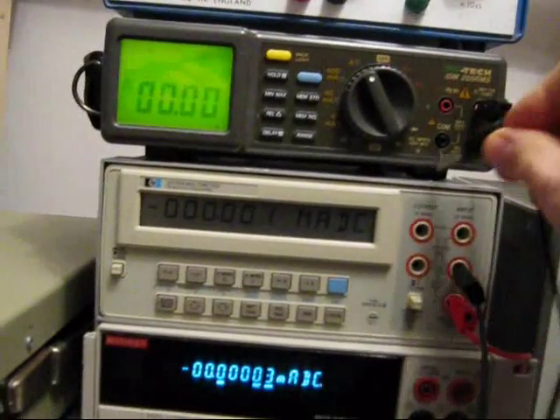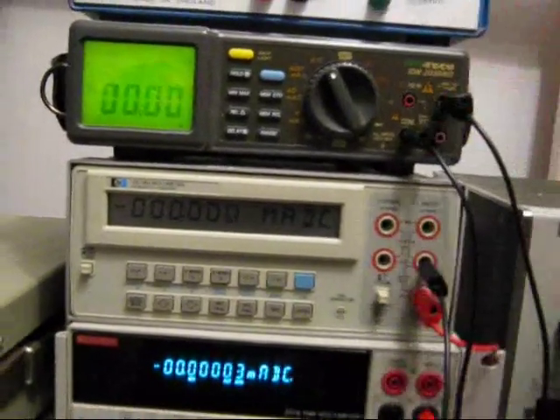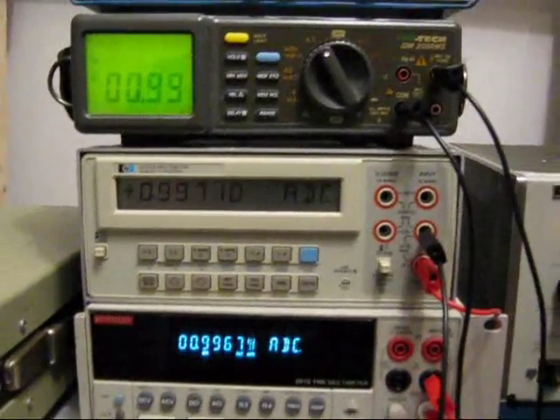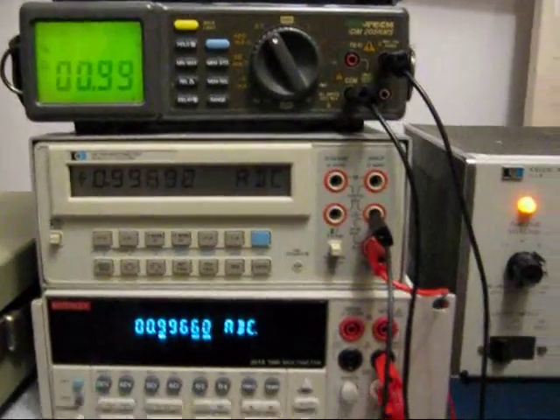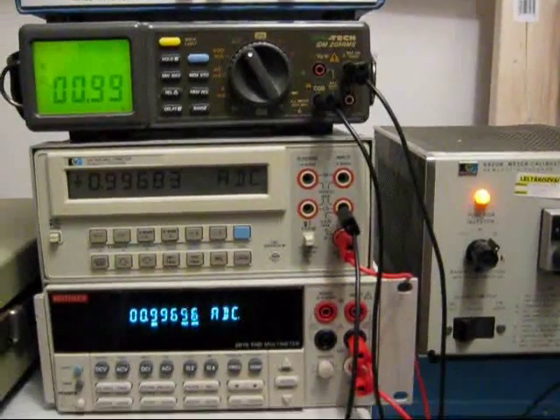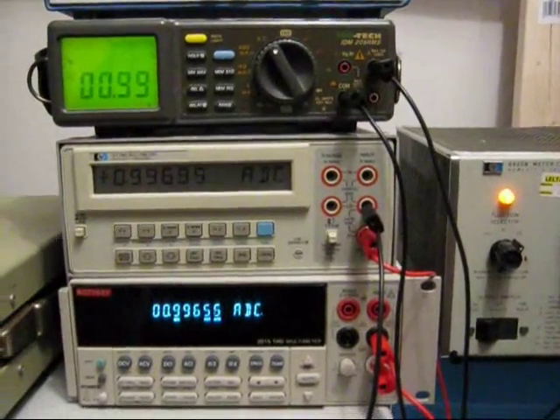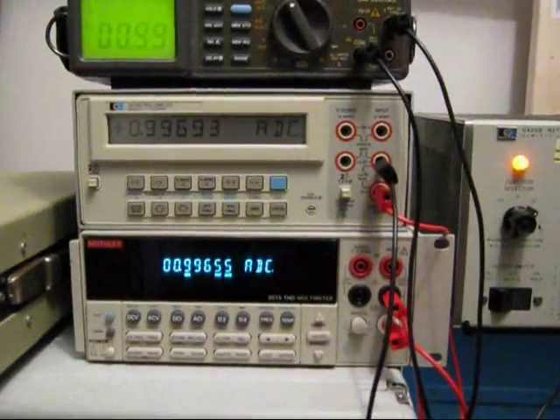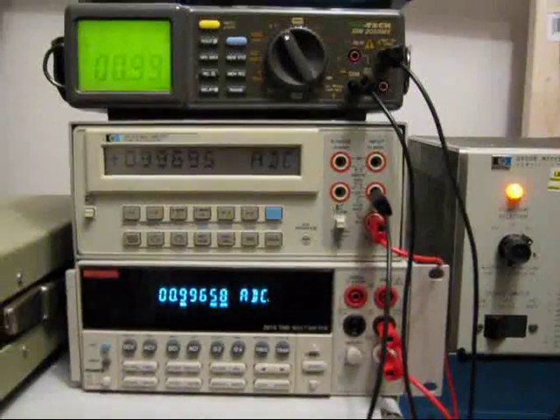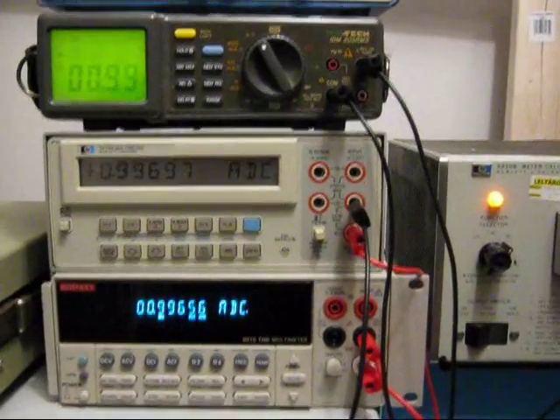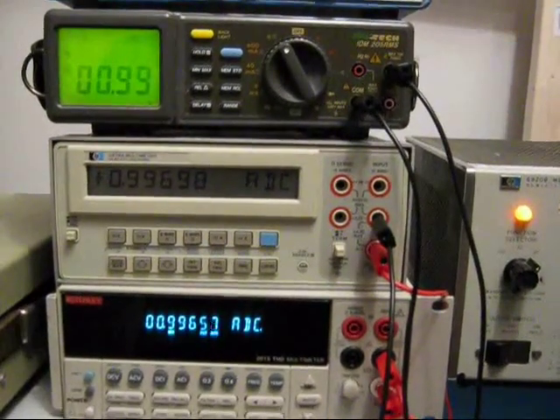We've gone in the high current port on the Isotec, and on 1 amp we've now got 0.996, 0.996 and 0.99.